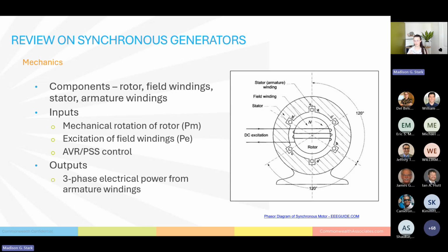So you have a few major components with a synchronous generator. You have a rotor, that's the part that spins, that's this part right here. On the rotor, you have what's called field windings. The field windings are excited via this DC excitation. And then you have the stator. The stator is the stationary part of the generator. And then on the stator, you have what's called armature windings, also known as stator windings, depending on who you ask. And those are located here.